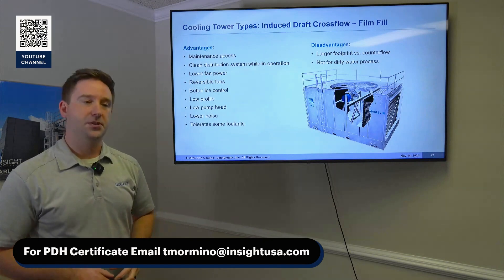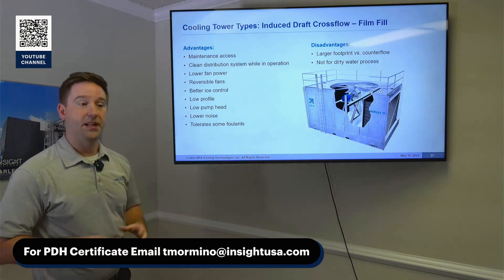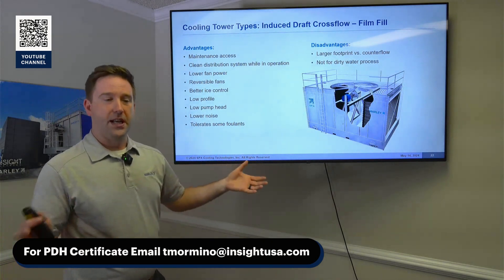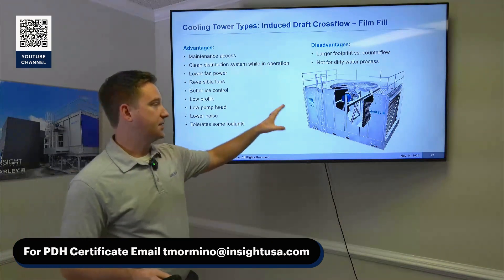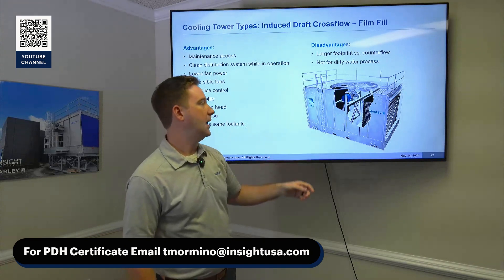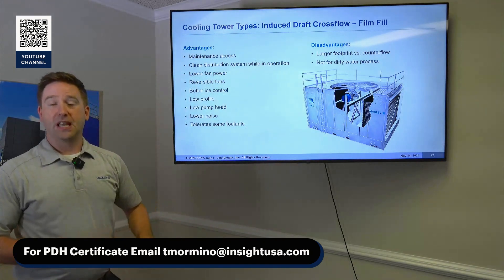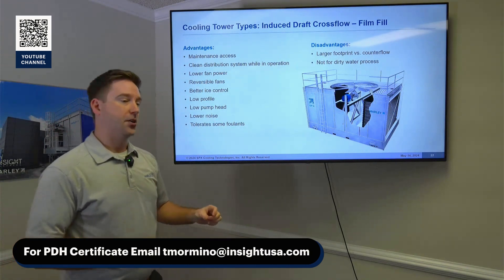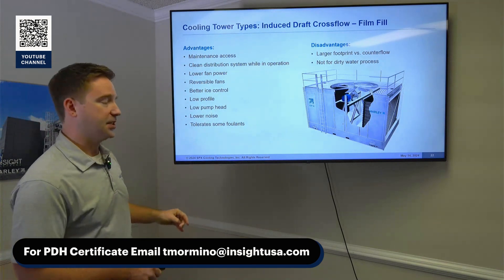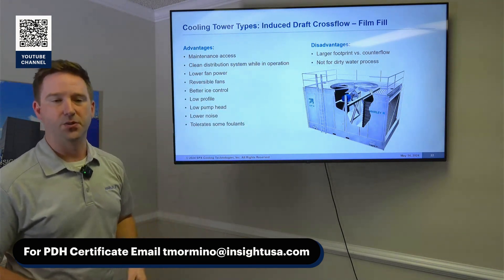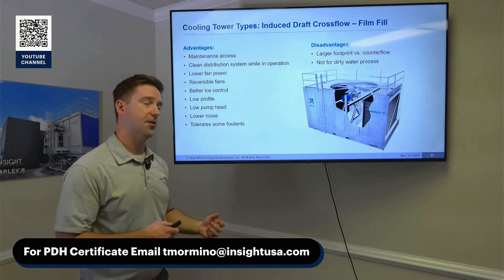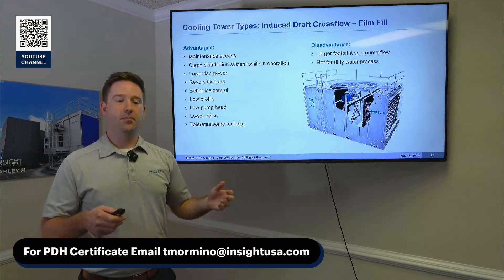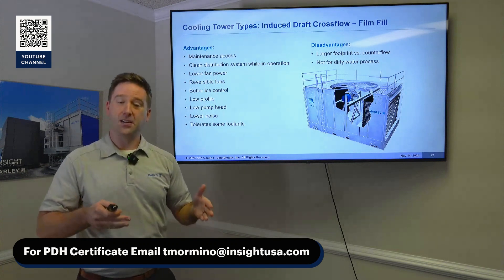Some advantages of a cross-flow tower: one of the biggest is its ease of maintenance. It's a larger tower, so you have a big plenum walkway, ladders to get to the top, and various mechanical access points. You also have much better ability to clean it — access to the fill, access to the basins, hot water, and cold water. From a freezing standpoint, you're able to operate it in a way that helps prevent freezing up the tower.